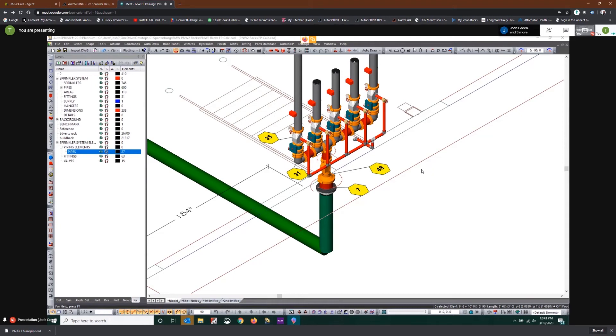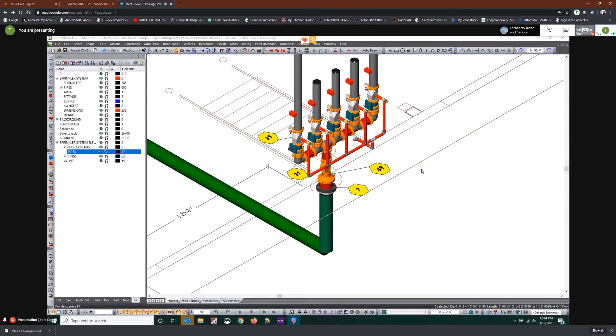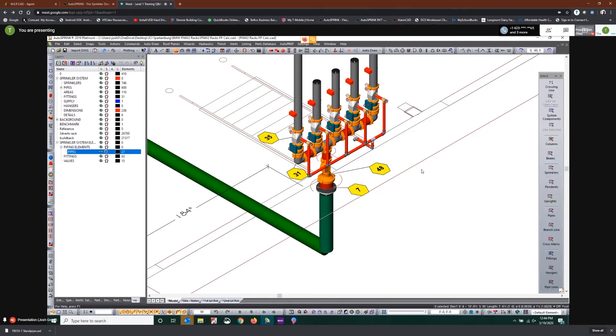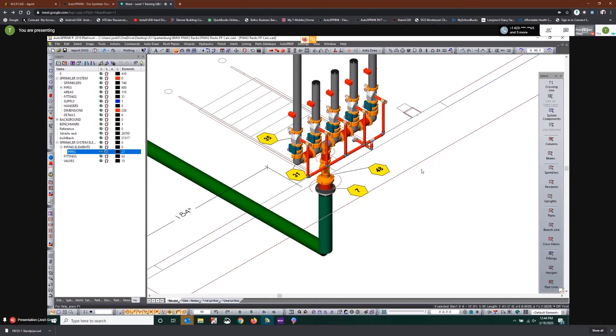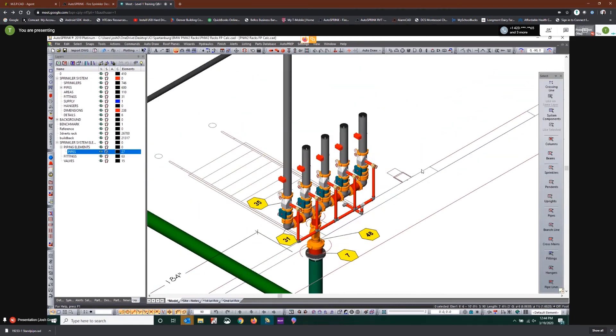The quickest easiest way to do this is to drop a hose valve at the top of that vertical riser pipe segment. And within the properties of that hose valve we're going to adjust the flow state to fixed flow state, but we might need to change it to a pressure dependent flow state depending on how the program balances that demand with this in-rack system.